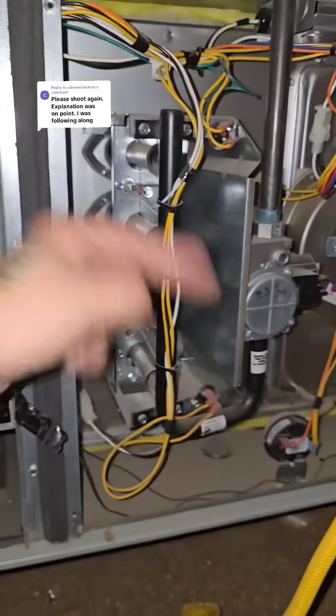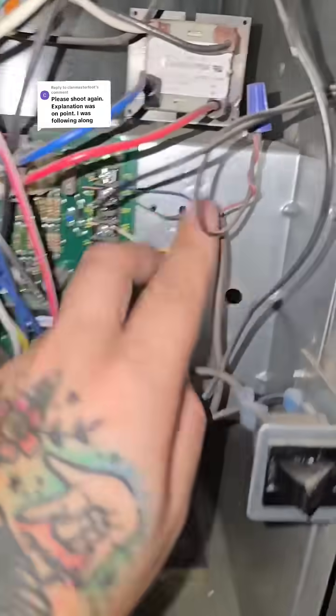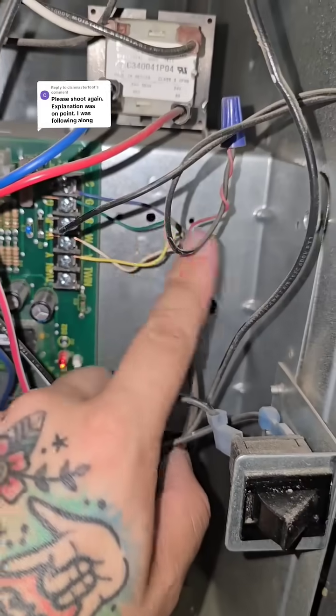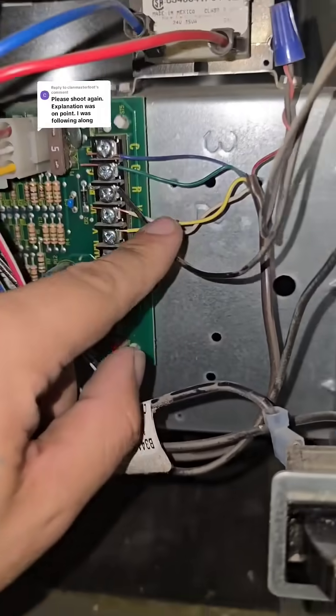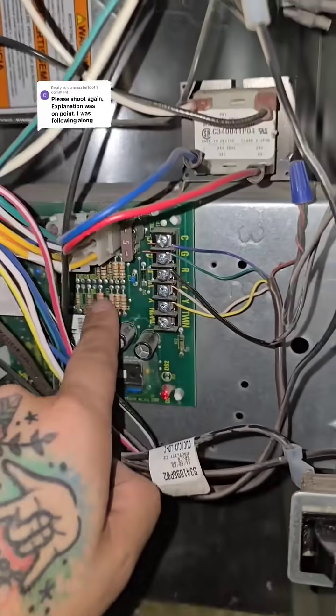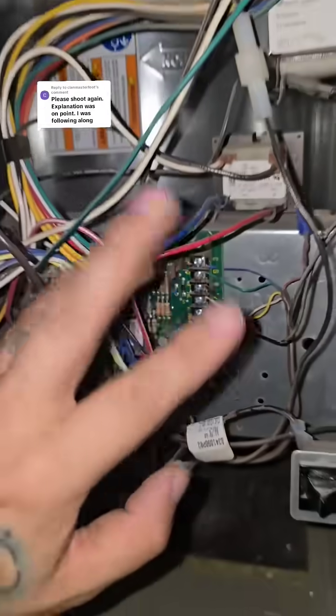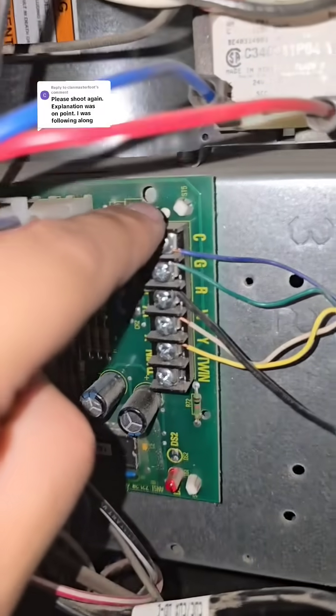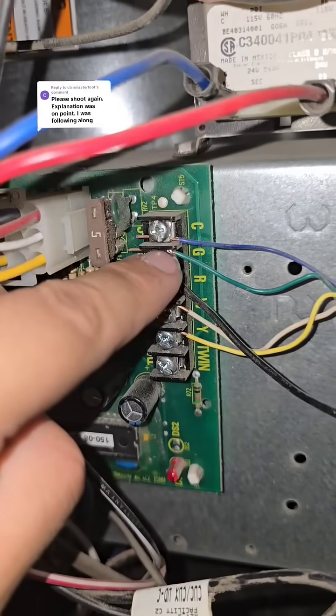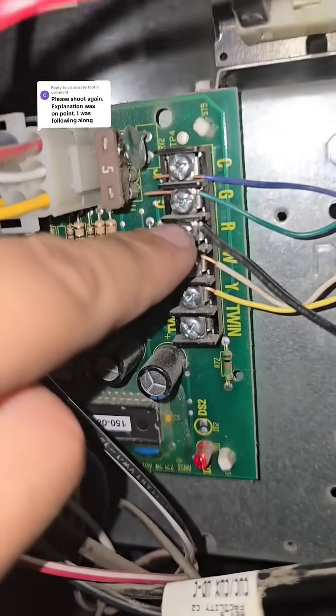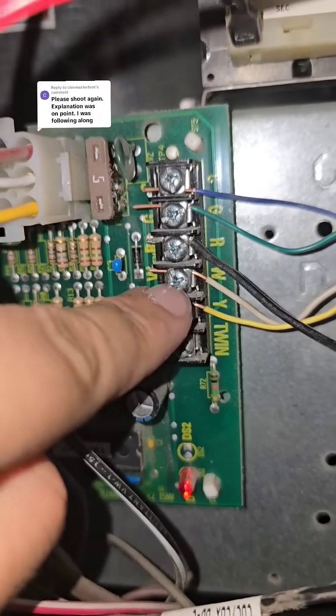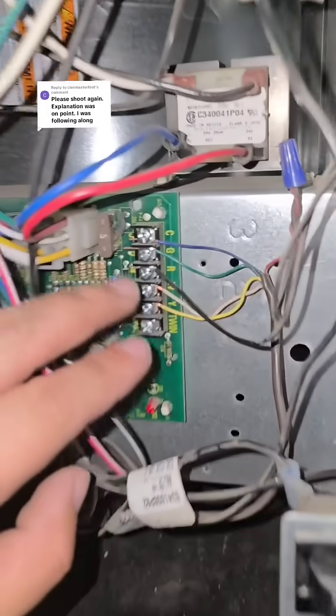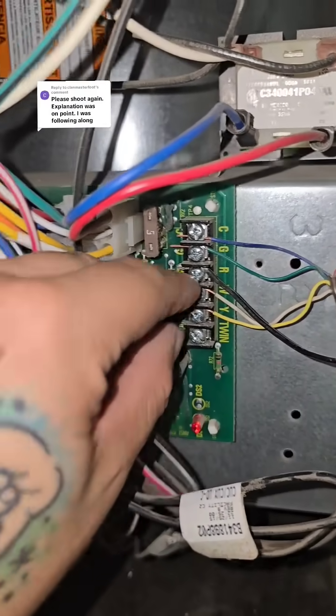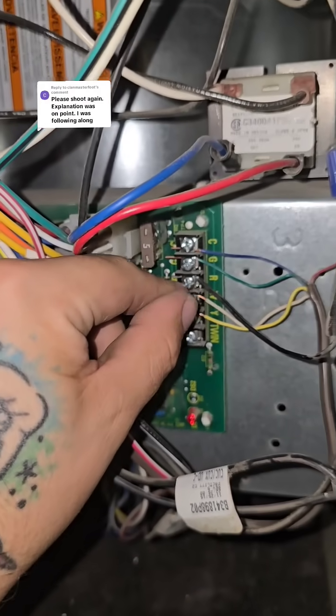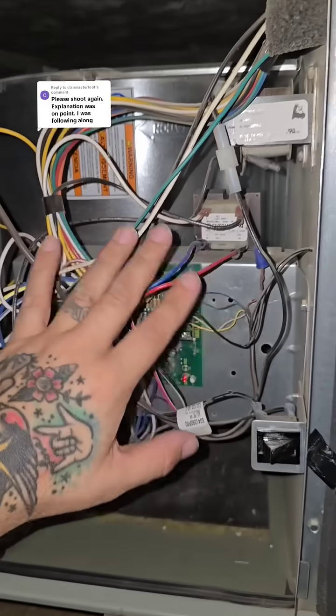Okay, so downstairs we have a thermostat. That thermostat is connected with this thermostat wiring. It's low voltage. That wiring goes to this control board. This is the brains of the whole operation. You got C, which is common, G, which is fan motor, R, which is power, W, which is heat, and Y, which is cooling. So that thermostat will take R to Y, R to W, R to green to tell the system what to do.